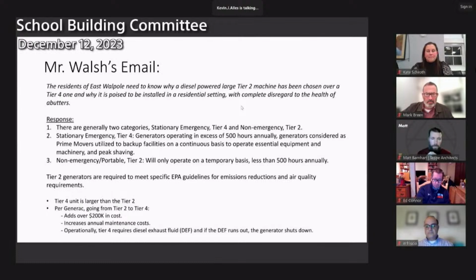And then a tier 4 requires a diesel exhaust fluid. That's what helps mitigate the exhaust leaving the unit. If that ran out, then the generator would shut down. So again, it adds a bit more maintenance and monitoring of the units versus a tier 2.